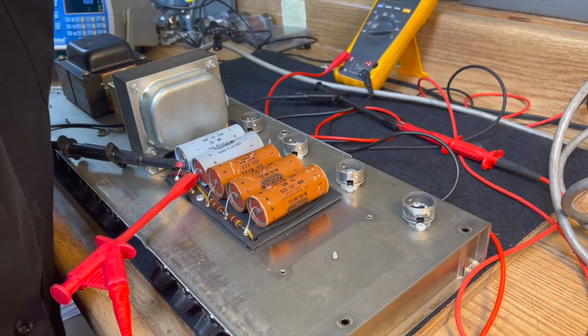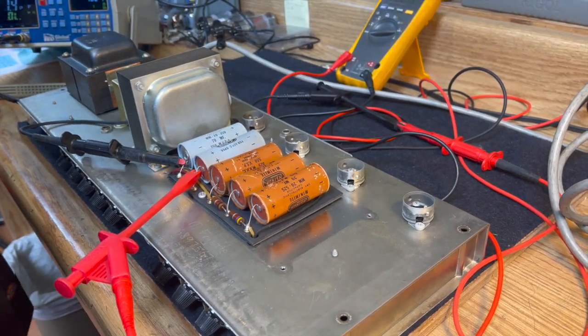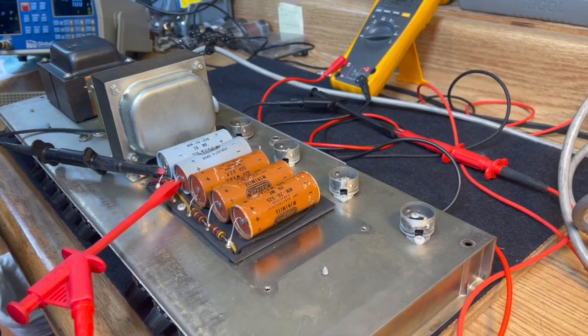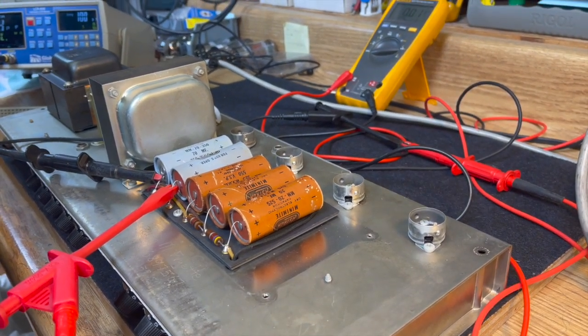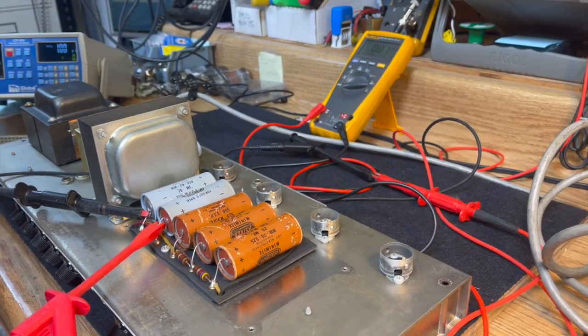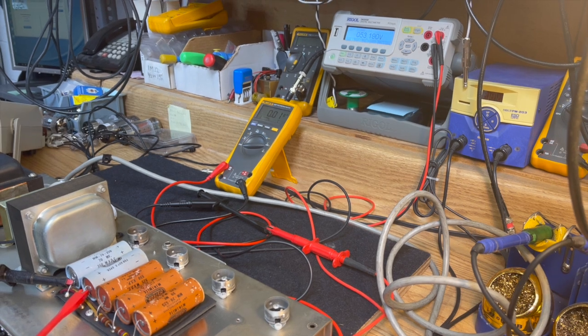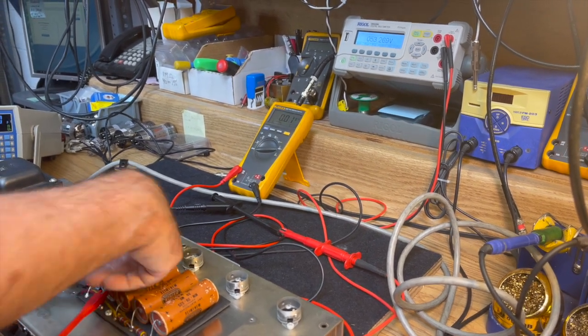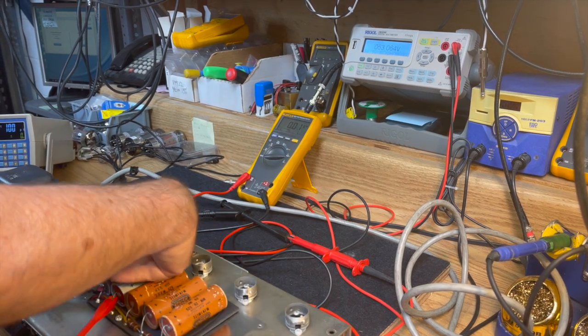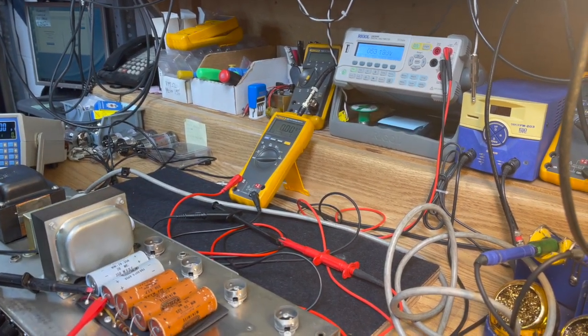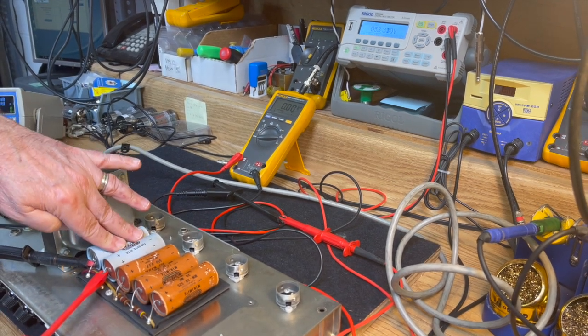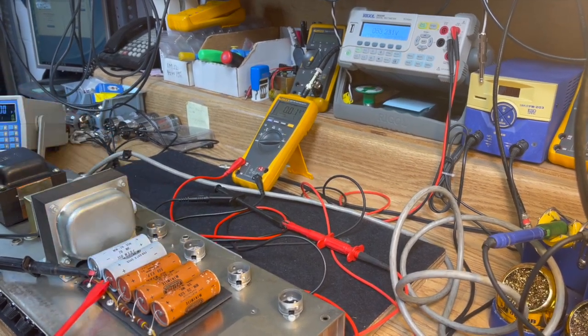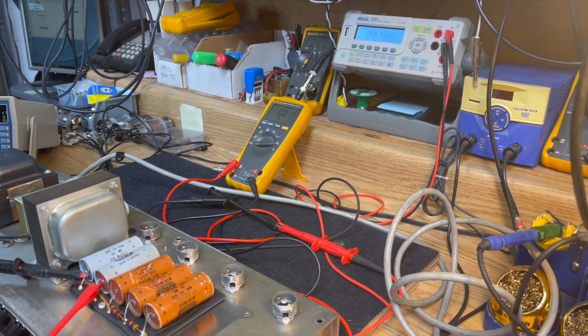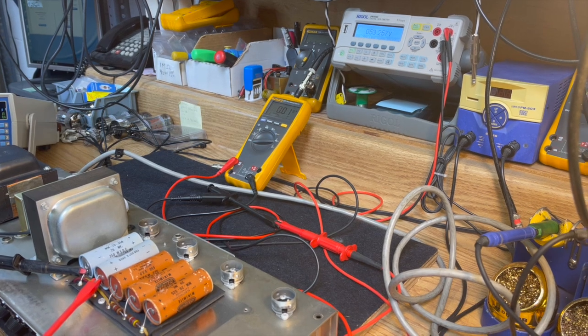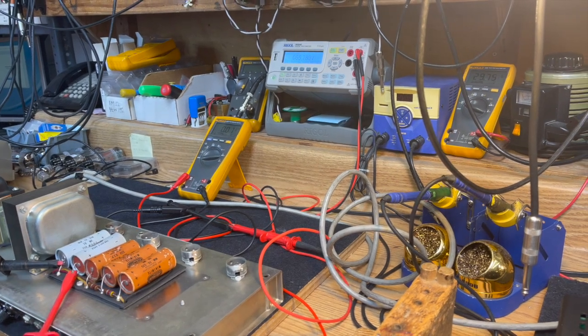So remember, we were at 53.2. Any variations at this point on that voltage are probably going to be caused by line voltage variations more than anything that's going on in here. Interesting. Okay. But we're nearby enough that we can come back and check it. There's no heat there. If I detected some temperature, I could put my temperature meter on there and we could monitor that to see if it was gradually rising or leveling off. But so far there isn't anything to measure, so no point in doing that. So we're looking good. We're going to leave this.